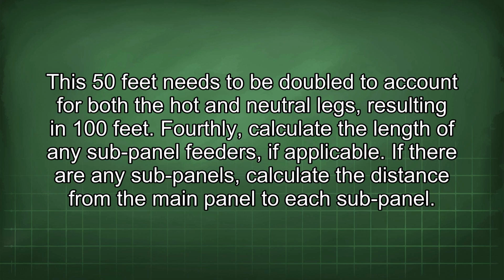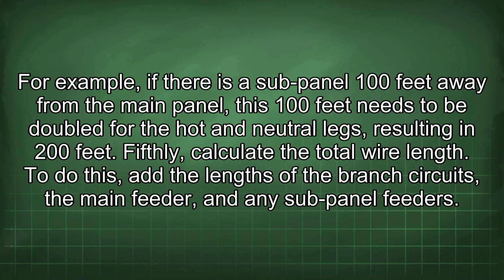Fourthly, calculate the length of any sub-panel feeders, if applicable. If there are any sub-panels, calculate the distance from the main panel to each sub-panel. For example, if there is a sub-panel 100 feet away from the main panel, this 100 feet needs to be doubled for the hot and neutral legs, resulting in 200 feet.